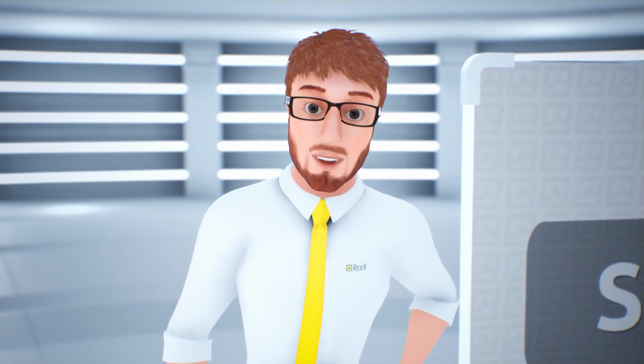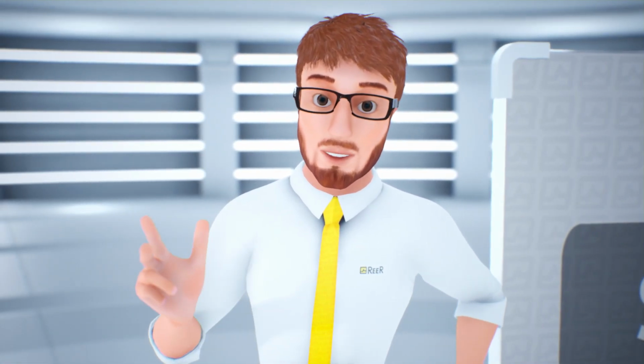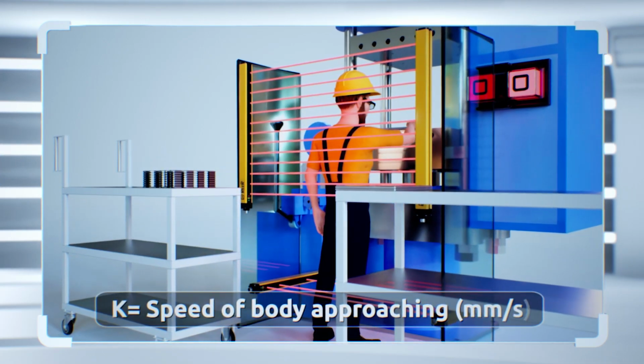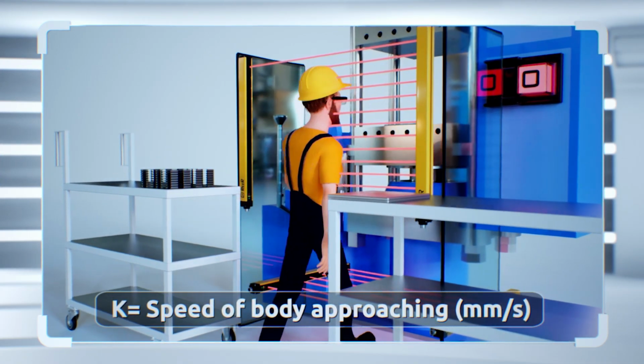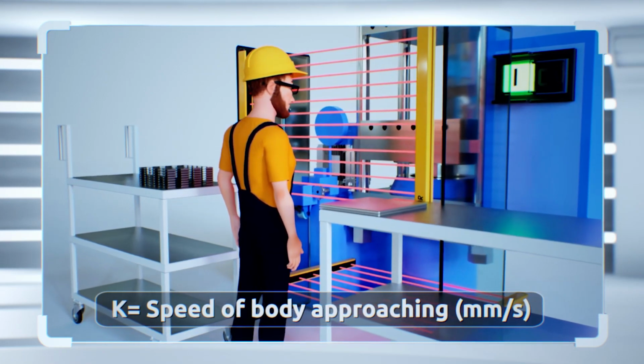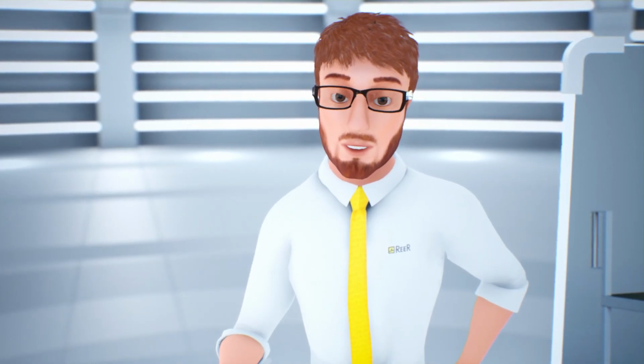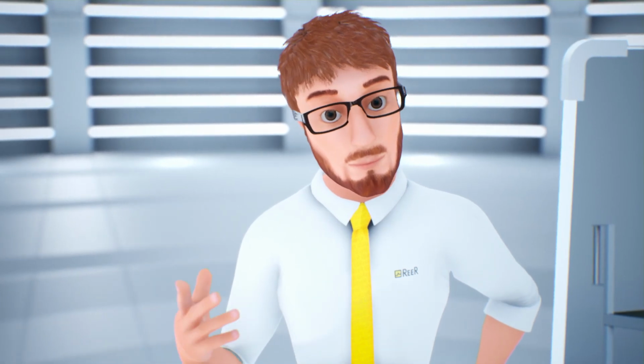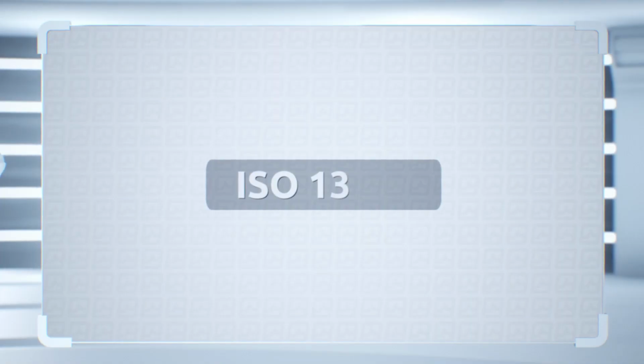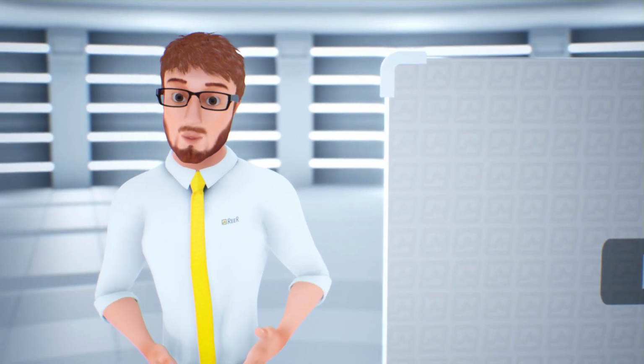The formula takes into account three main factors. 1. Speed at which the body is approaching the dangerous zone, K coefficient. This calculation is expressed in millimeters per second, and the value is defined by the norm ISO 13855. 2.